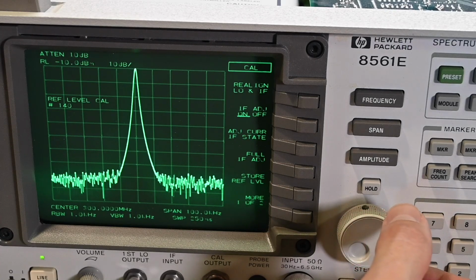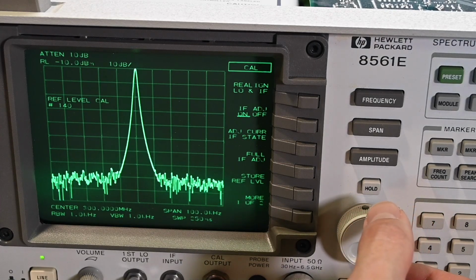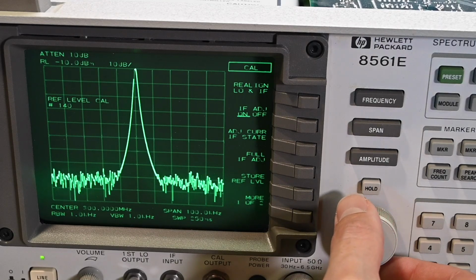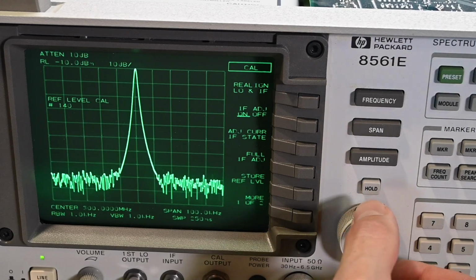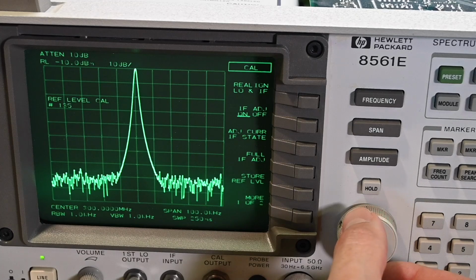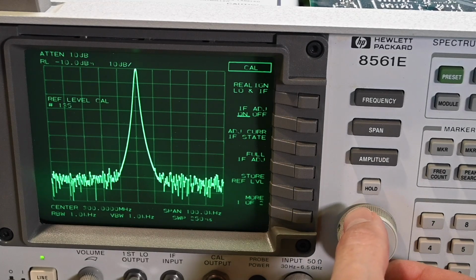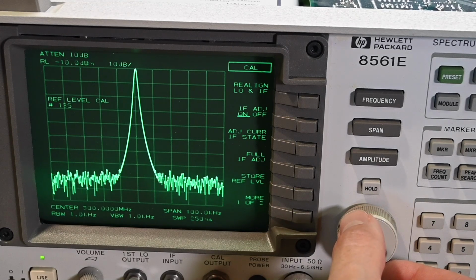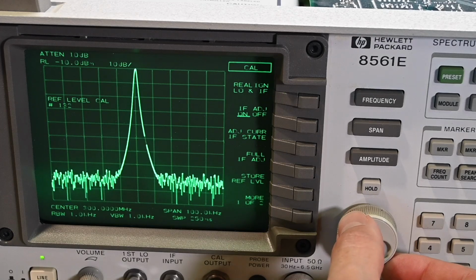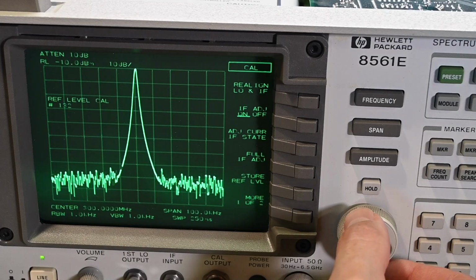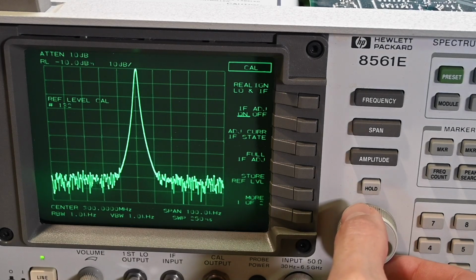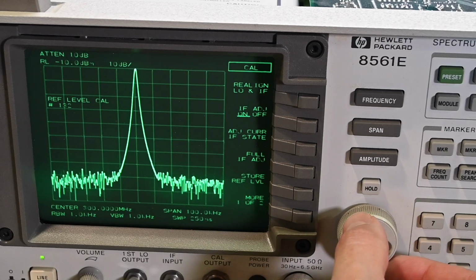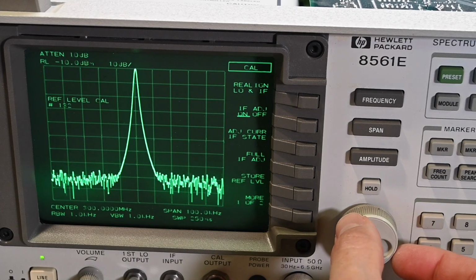Ideally, this reference level value should be close to 0. That's what the service manual calls out. So it's nice to see that we can actually bring it back down from where it was. The old A10 module would have affected this because the signal, of course, passes through that module, and for whatever reason it may have had some more attenuation because the reference level was basically being increased higher than it needed to be.